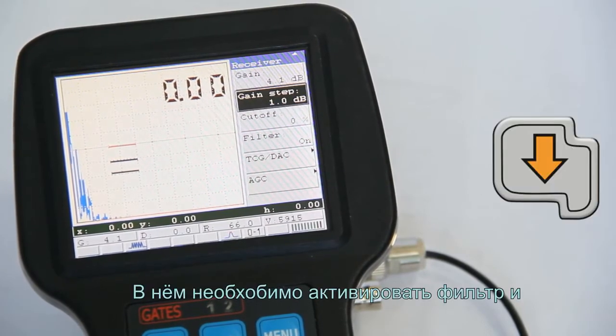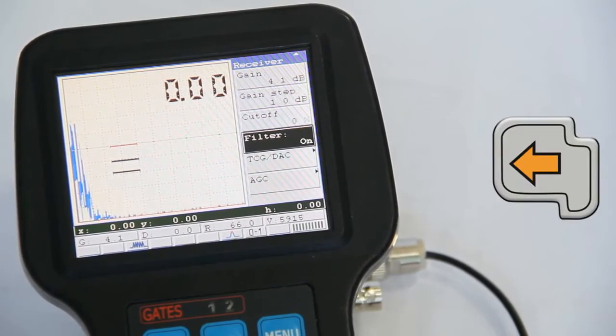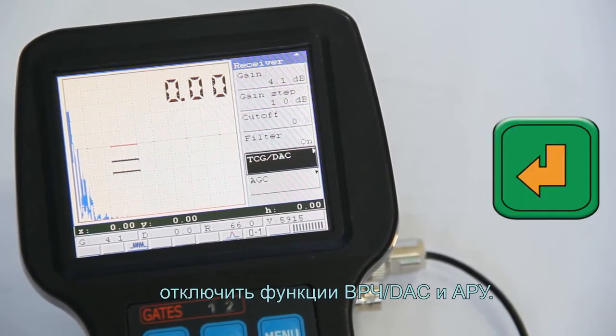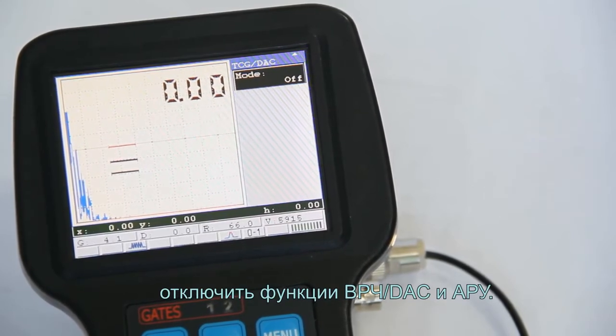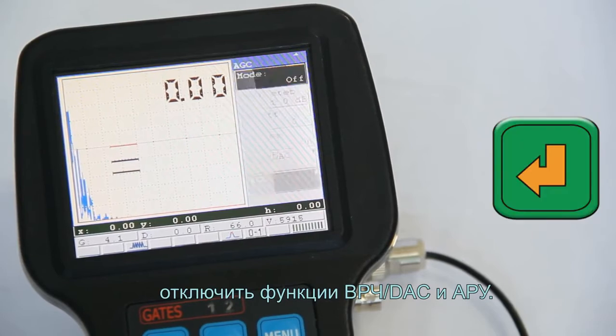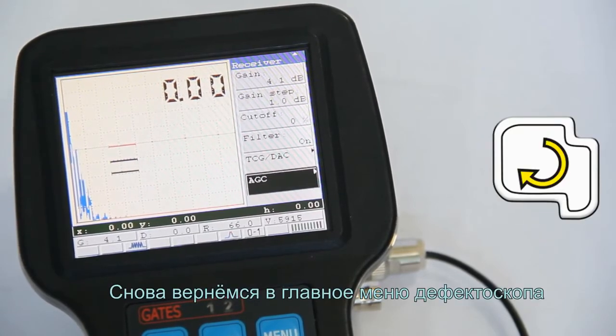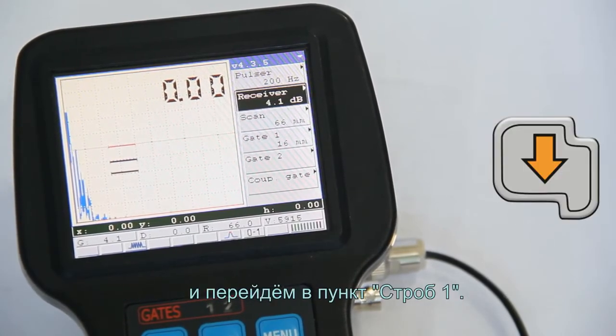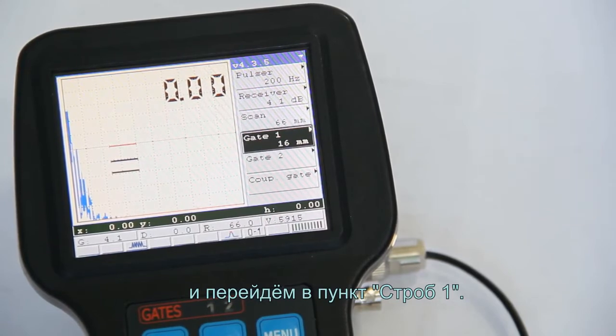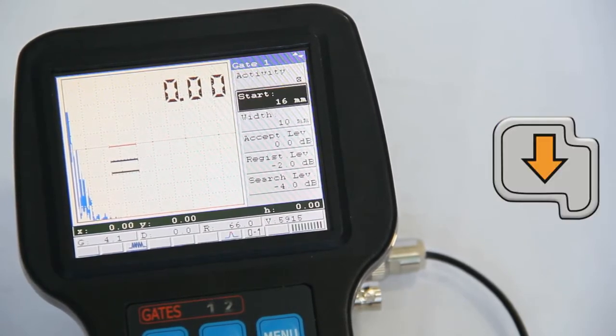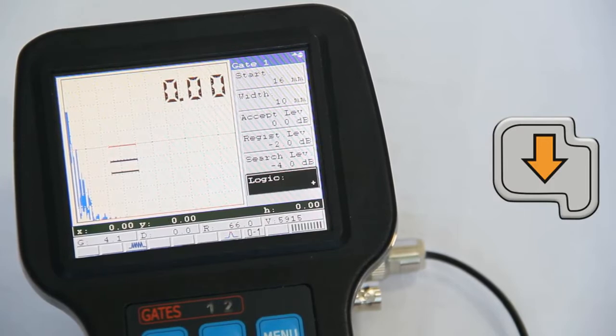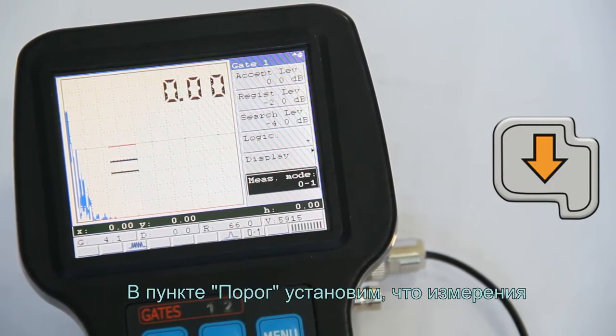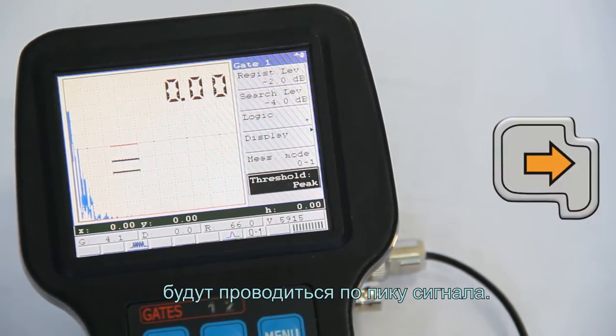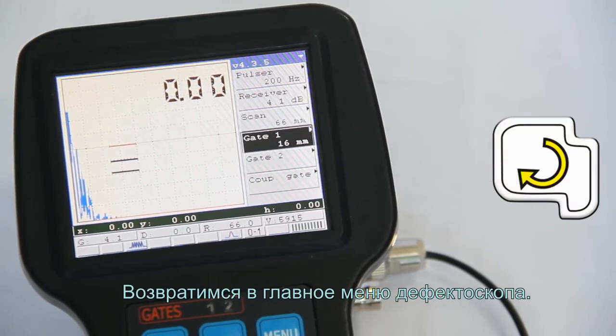Enter the receiver menu item. Here activate the filter and switch off the TCG/DAC and AGC function. Then return to the main menu of the flaw detector and move to the Gate 1 item. In the threshold item, set the measurement to be carried out by the signal peak. Return to the main menu of the flaw detector.